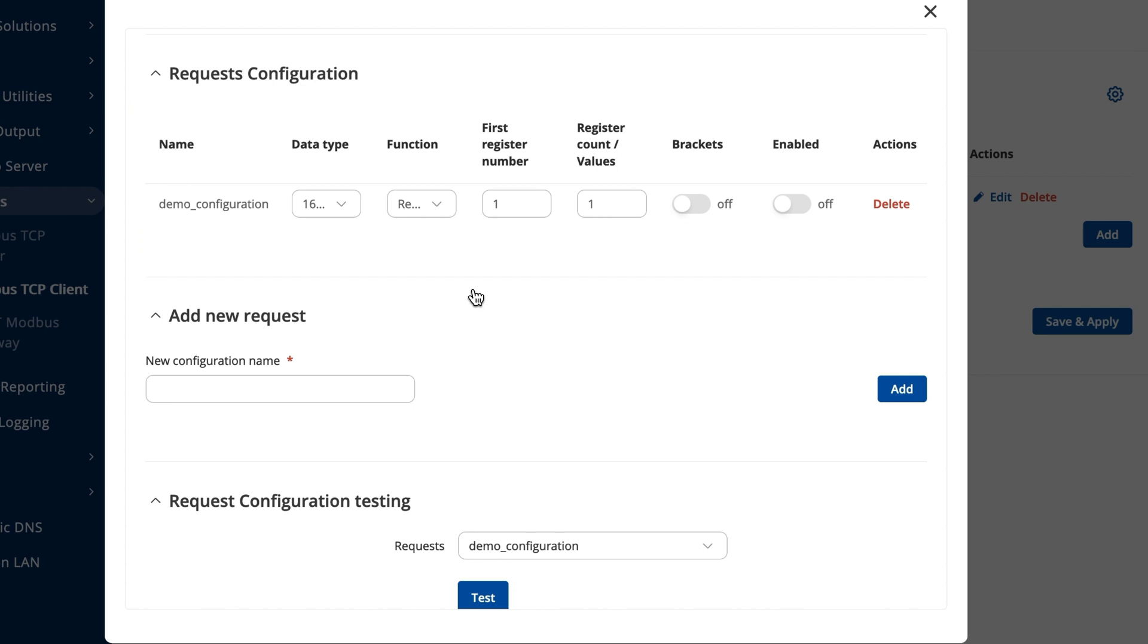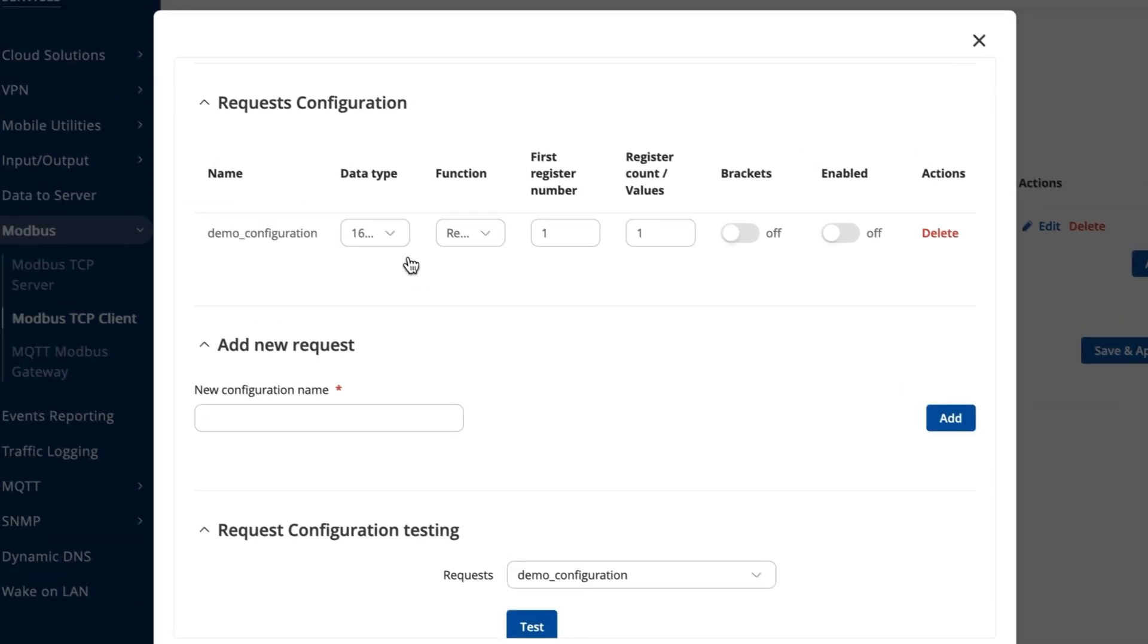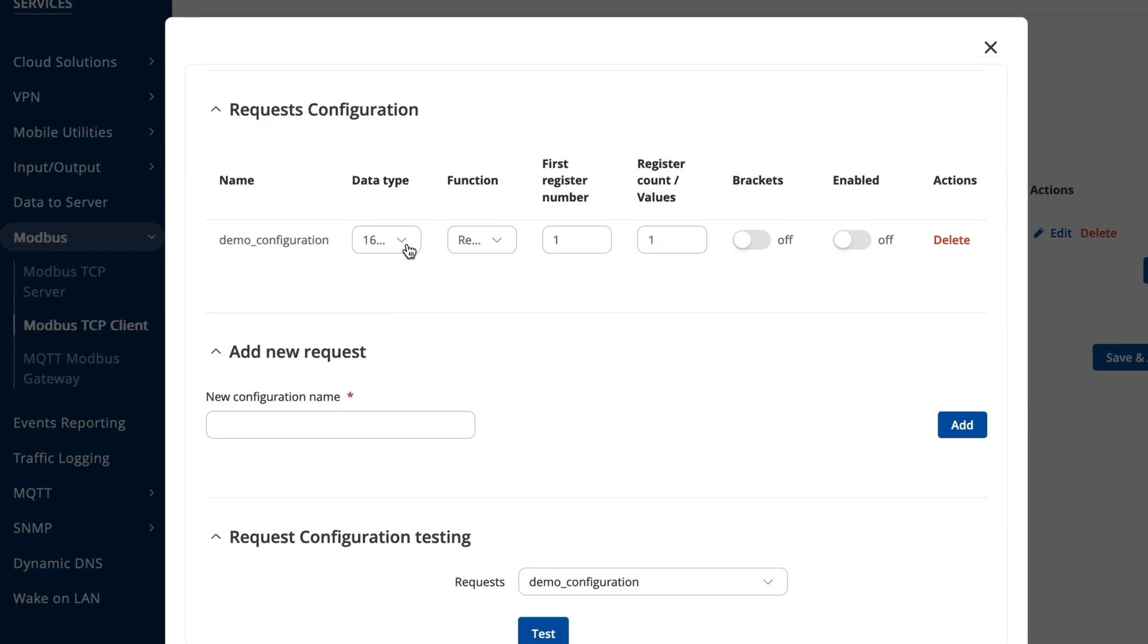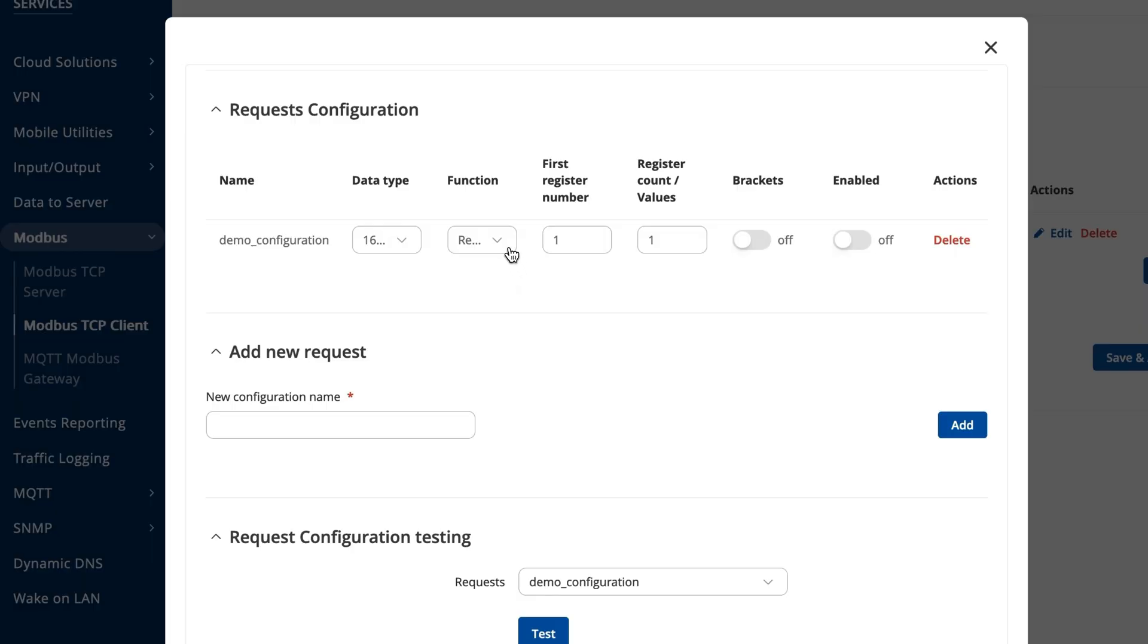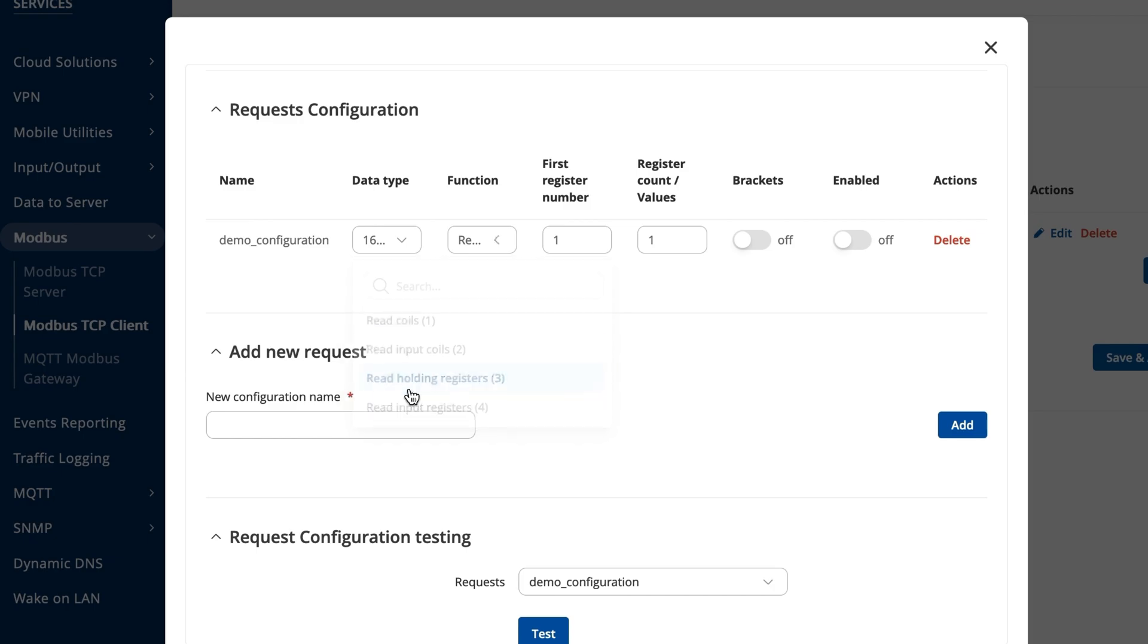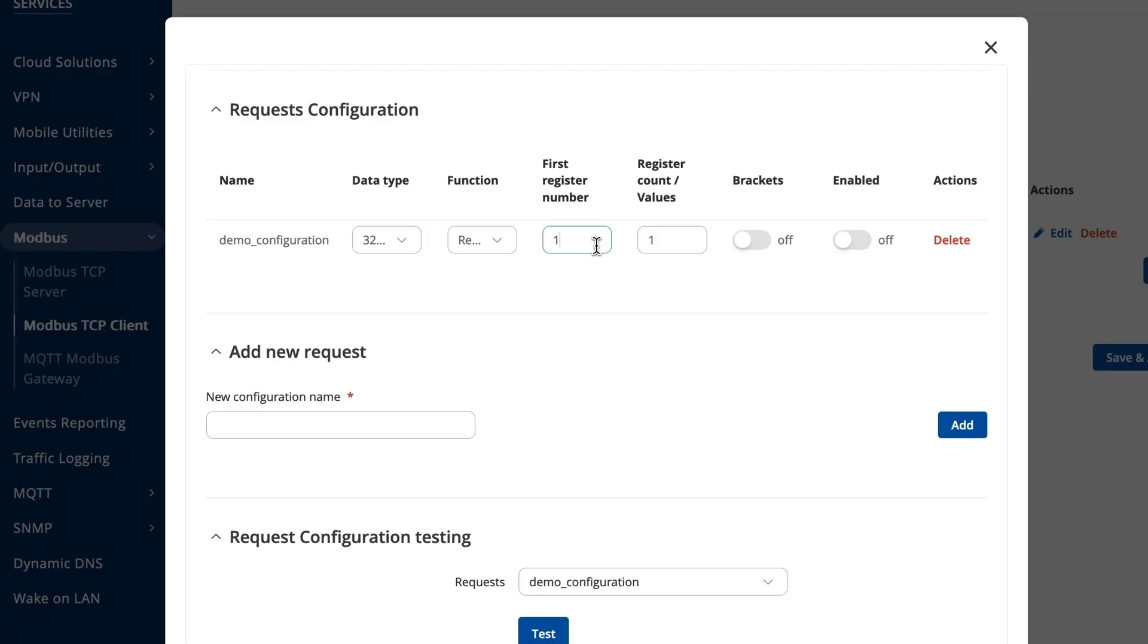The data type specification determines how the obtained data will be interpreted. You can learn more about it on our wiki page, linked in the description. In the functions section, choose the read holding registers option, which indicates that we'll be scanning information from the registers. The specific register number you need and the number of registers can be found on the same wiki page mentioned before.